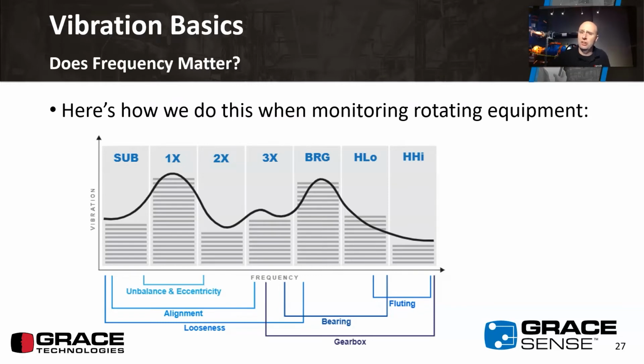So when we're monitoring your rotating equipment, we're pulling bands that associate with different defects, and we're just looking at how much power or amplitude is present in each of those frequency bands. We end up with a chart that looks like this, and if you start to see spikes in different bands, that can tell you something -- from an eccentricity issue to, oh, this is actually probably a bearing issue or a gearbox issue.